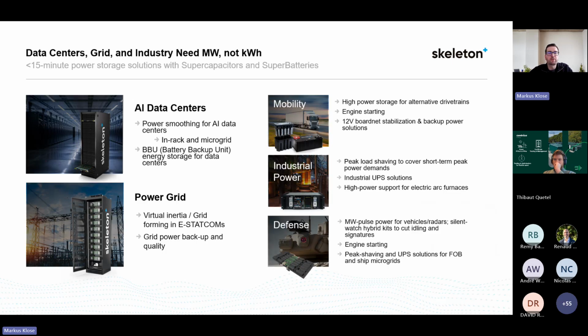So where are these systems used? As mentioned, in AI data centers for power smoothing, both at rack or grid level. You can also put these into so-called battery backup units, similar to UPS systems, but they will not really replace UPS systems. Battery backup units typically last up to 5 minutes maximum. After that, other solutions take over. So this is really just short time coverage in the case of a power outage.